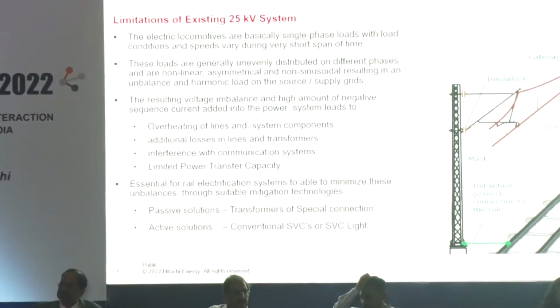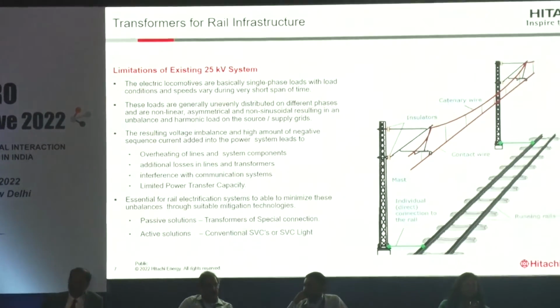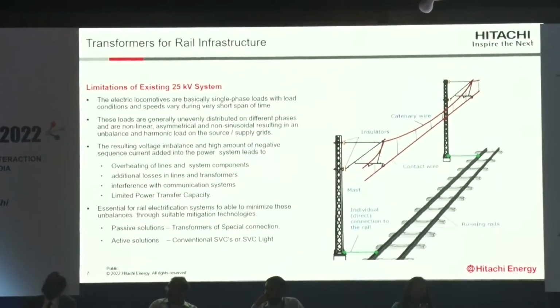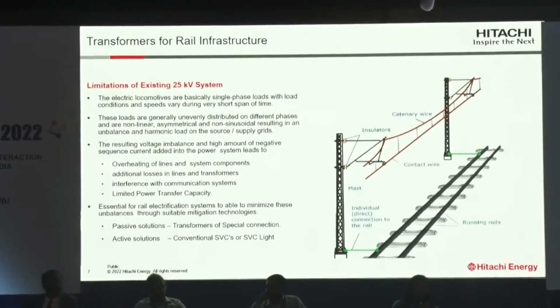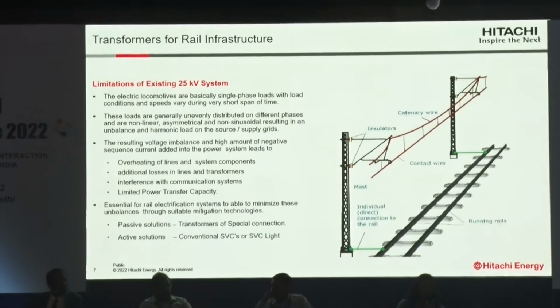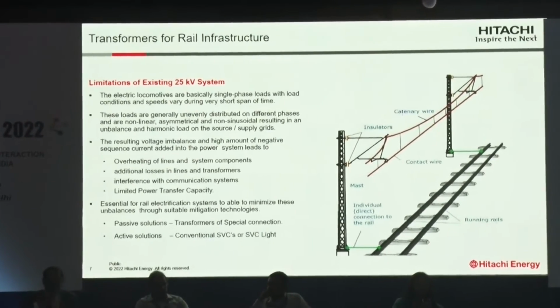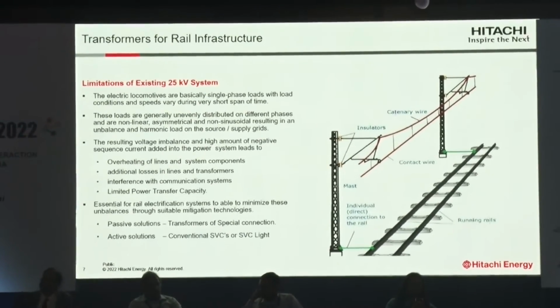This creates an unbalance, because normally the grid available nearby is a 3-phase grid. When we are loading only 2 phases out of the 3, that creates an unbalance, and there is a voltage regulation issue that comes up. That becomes predominant when we talk about high-speed rails and when the catenary load or locomotive load is going to increase.